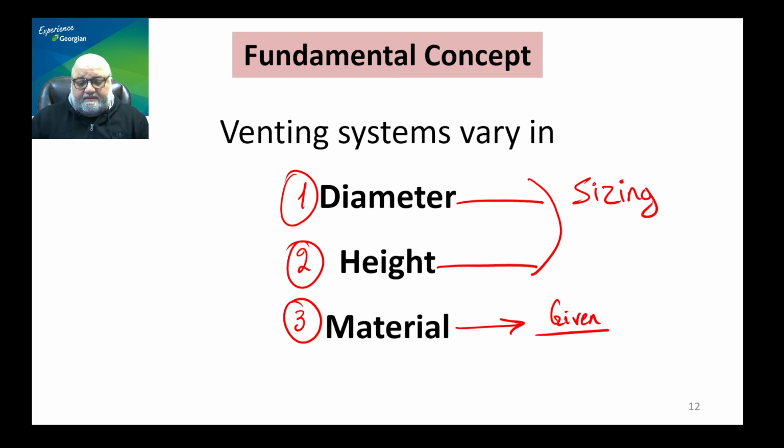To understand better, the only time you're going to be asked what material to use is either when it is a rule, like for example, recessed wall heaters shall always use type BW venting systems. Why? Because the code book says so. Or, for example, if you're going to use system 636, there are 4 different categories of it depending on the temperature of the flue inside of it.